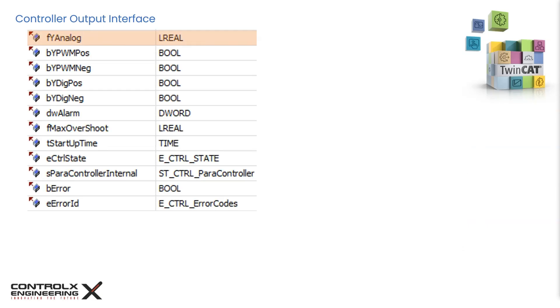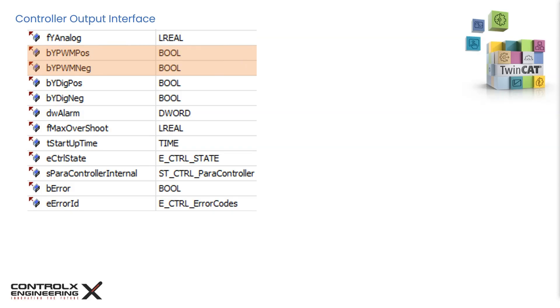This is the control value in analog form. It can be scaled from 0 to 100 by setting the Fy min and max parameters of the controller parameters that we just reviewed. These are the control value outputs in digital form and can be used to control solid state relays by using pulse width modulated output control. The on and off timing of the digital output controls the duty cycle of the PWM signal. The positive and negative outputs are used for heating and cooling respectively. If your application only does heating, then just use the positive PWM output to control the heating SSRs.